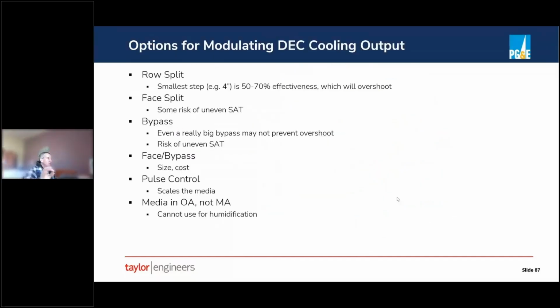So to modulate the cooling output, we talked about the bypass. There are other ways to modulate the output. One is to split it into rows. And so you can have 8-inch deep media that's row split, in that it's basically two 4-inch sections, and you can have one 4-inch section that's 50 to 70% effectiveness. The problem with row split is that even then you get most of the cooling with just the first couple inches. And so you can still have issues with overshooting. So we're not big fans of row split.